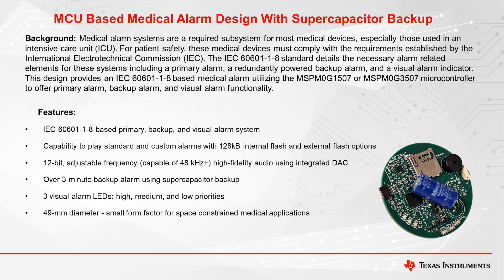Medical alarm systems are a required subsystem for most medical devices, especially those used in an intensive care unit. For patient safety, these medical devices must comply with the requirements contained in the IEC 60601-1-8 standard. This standard details the necessary alarm-related elements for these systems, including a primary alarm, a redundantly powered backup alarm, and a visual alarm indicator.